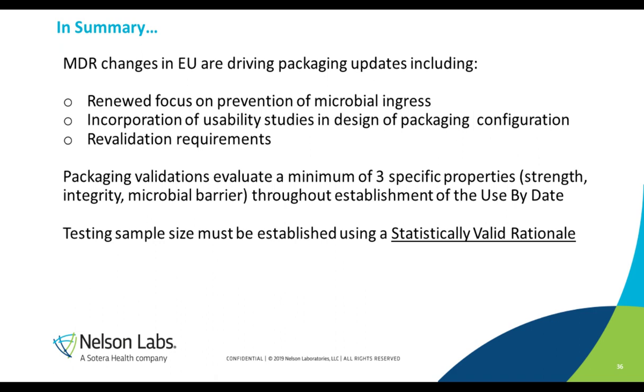When you're looking at different packaging validations, it's very important to make sure that you do address all three properties, strength, integrity, and microbial barrier, and that you evaluate them through the establishment of your use by date. And then finally, we did touch on establishing a statistically valid rationale and some of the approaches that you can use to put that down and get it documented.